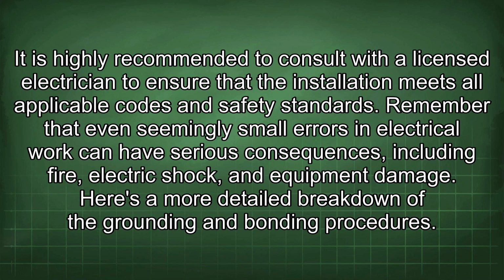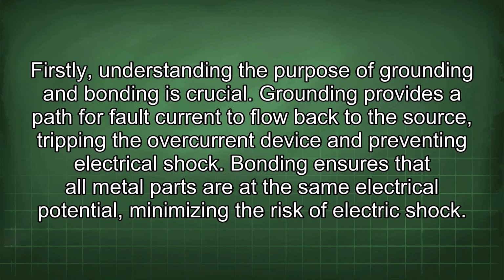Here's a more detailed breakdown of the grounding and bonding procedures. Firstly, understanding the purpose of grounding and bonding is crucial. Grounding provides a path for fault current to flow back to the source, tripping the overcurrent device and preventing electrical shock. Bonding ensures that all metal parts are at the same electrical potential, minimizing the risk of electric shock.